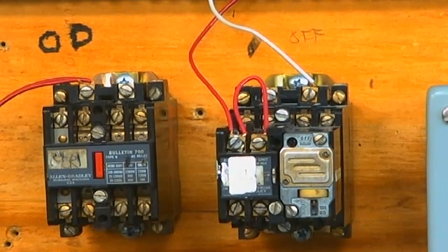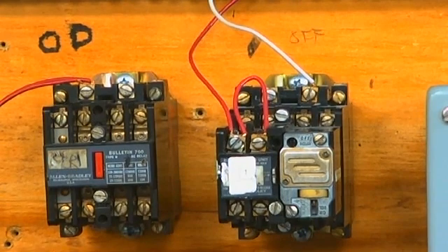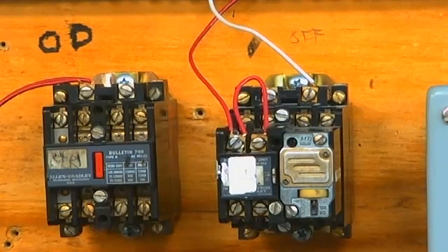I said the disconnect, not the coil. So I'm turning the disconnect. I just energized this thing. The red one's normally closed, so the red one will turn on. All right, now I push the push button down and energize that coil. What happens? This is the most confusing part for people because you have not just normally open and normally closed, but you have on delay versus off delay. Well, after 3 seconds, the green light would come on.